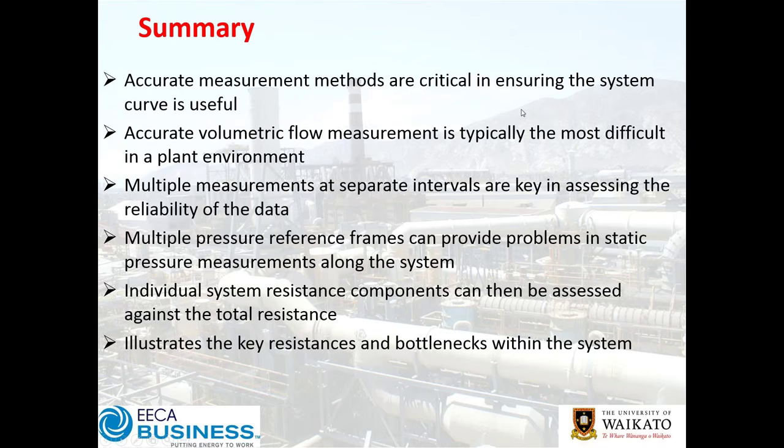Accurate measurement methods are critical. Volumetric flow measurement is typically the most difficult — looking at other process variables could be useful. Do multiple measurements to test fidelity, repeatability, and reliability. Multiple pressure reference frames can be tricky, particularly for systems going through multiple closed rooms or zones. System component analysis helps guide us toward minimizing total resistance and identifying key bottlenecks.